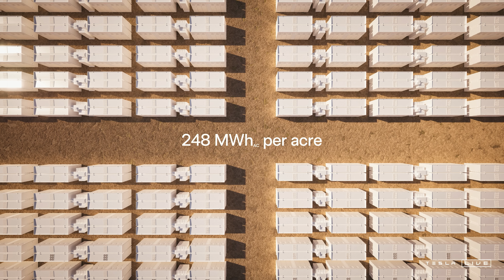It's no secret the industry has been trending towards higher and higher energy density containers, but as we developed this product, we realized there was a fundamental problem with that approach. Once you exceed the maximum shipping weight, you introduce risky and costly transportation permits and trailers, or you resort to on-site assembly, installing batteries in the field, validating, integrating, commissioning them, and not doing that in a factory setting. The metric that actually matters is site-level density, which includes the clearances on the ground needed to install and service your product.